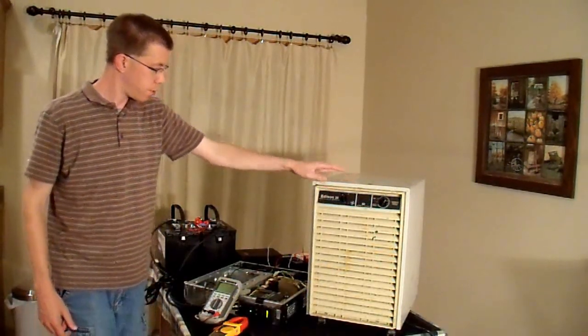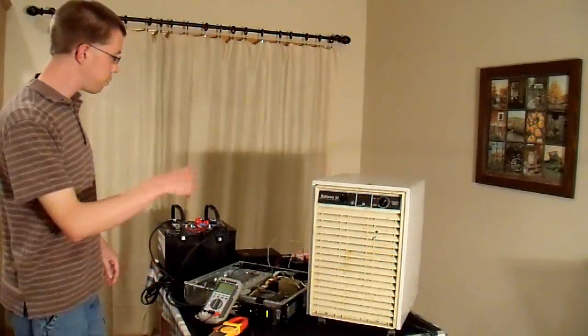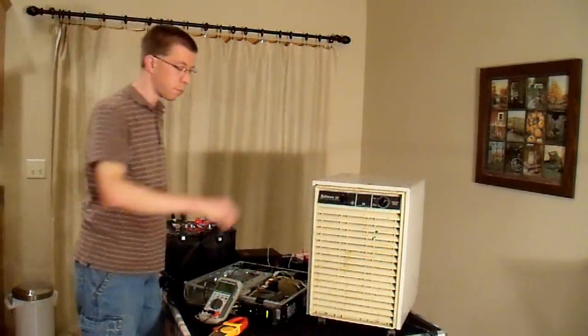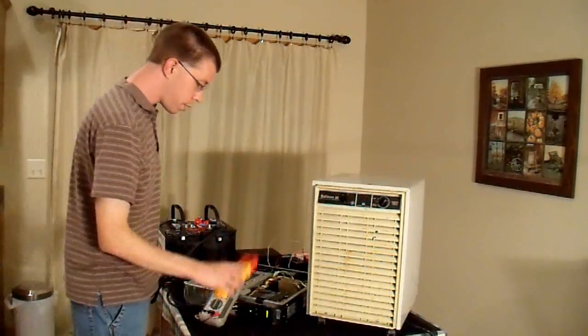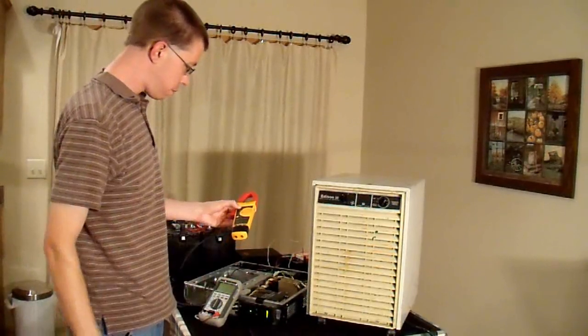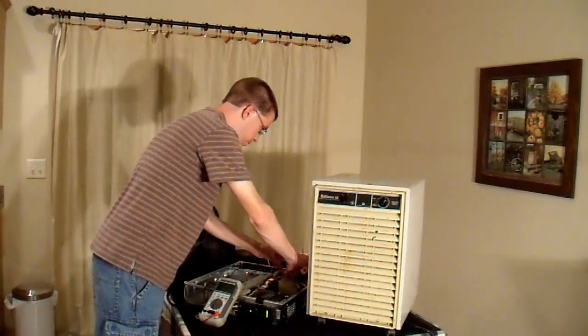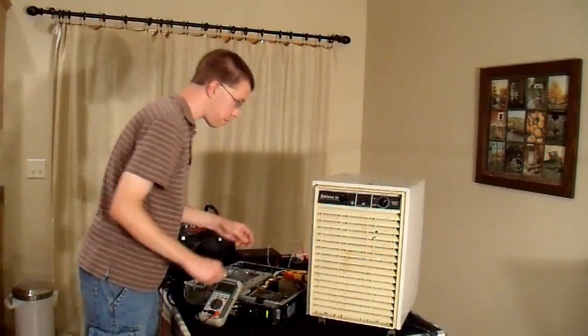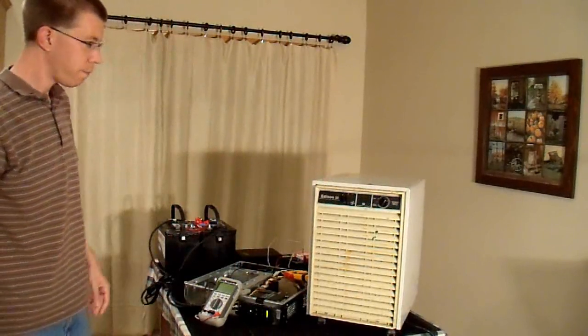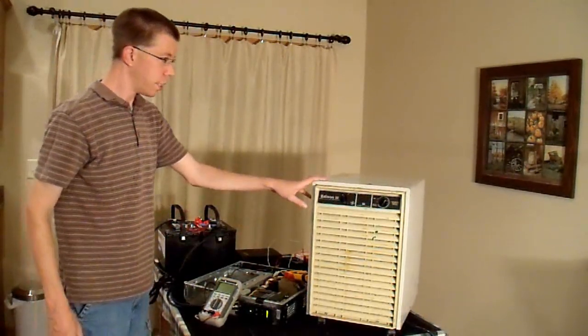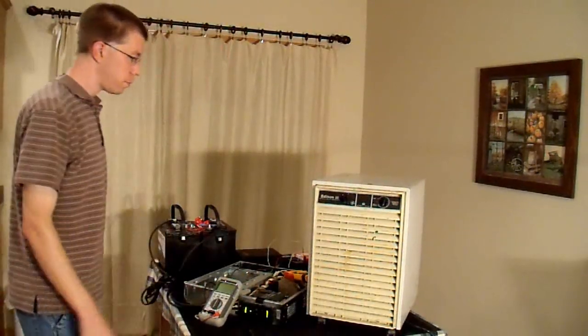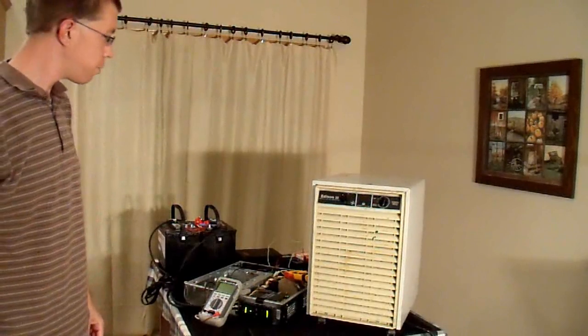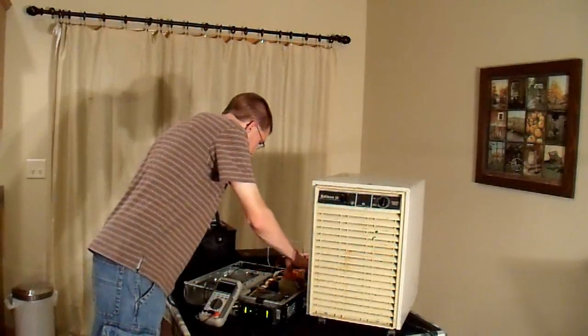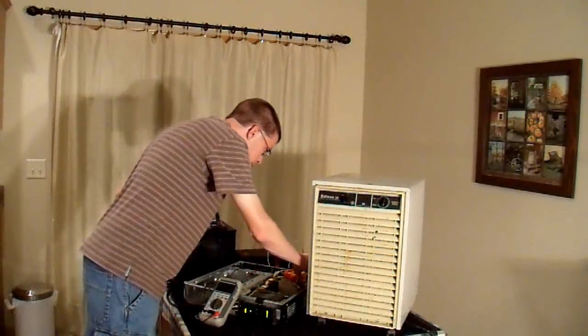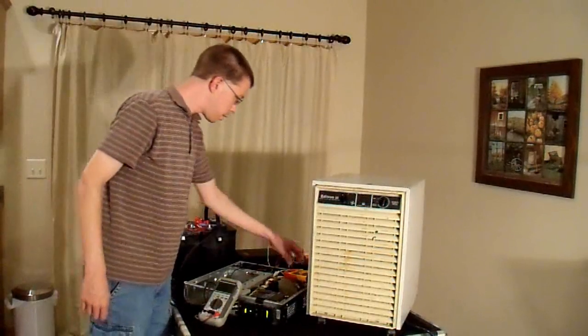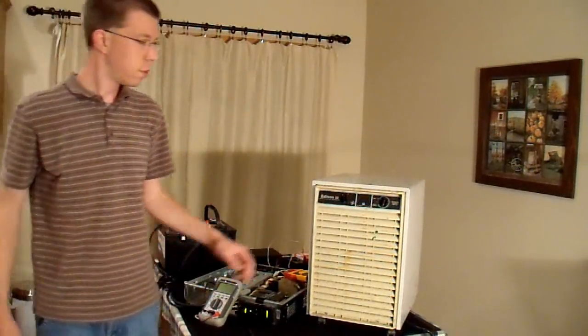So the first thing I want to do is get this all set up. I have the UPS plugged into the wall. Looks like my dehumidifier is plugged into the UPS, and I'm just going to flip on my meter here, flip that around one of these wires that goes out to the dehumidifier, and see what kind of current draw this thing actually takes. So it's operating off wall power right now. I'm on DC amps, no wonder it doesn't show up. Alright, so it takes about 6.5 amps when operating.